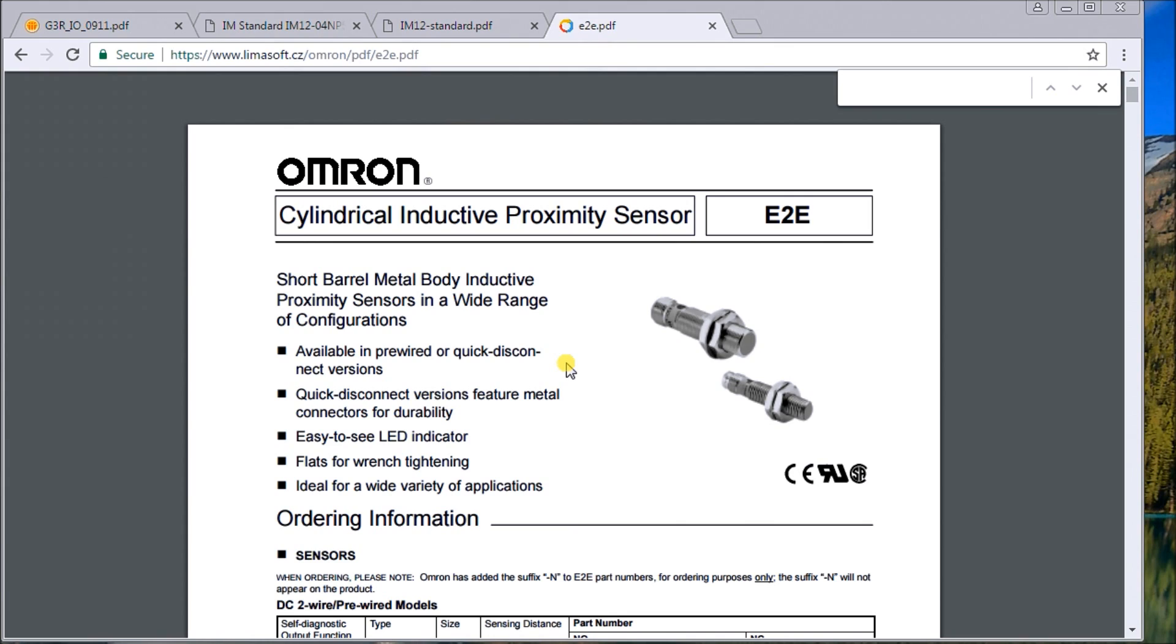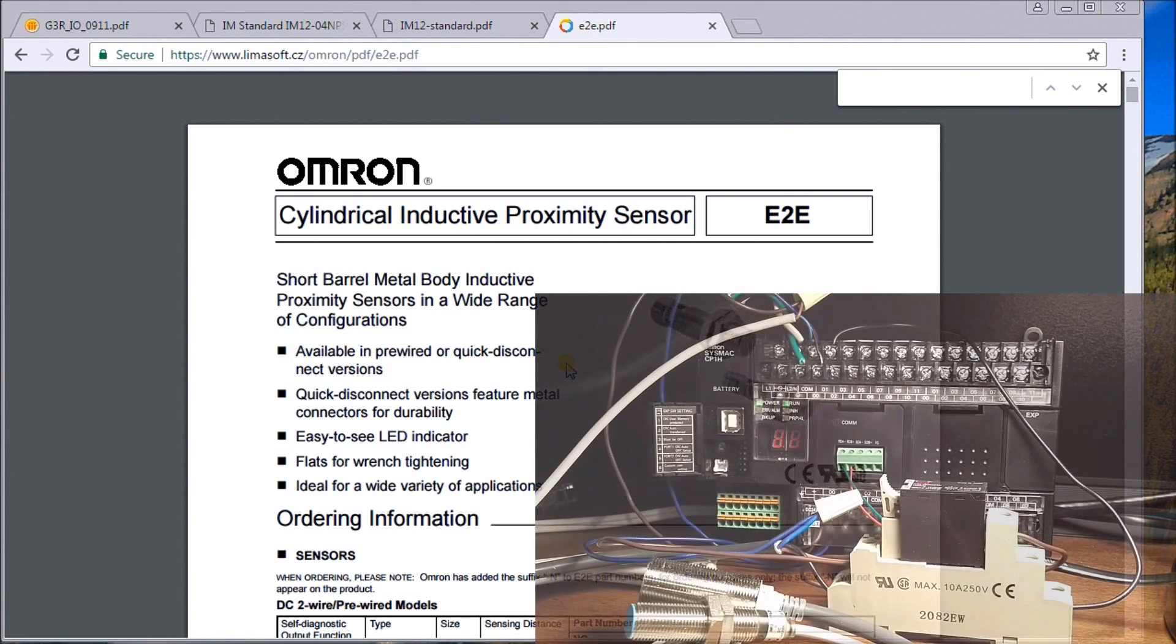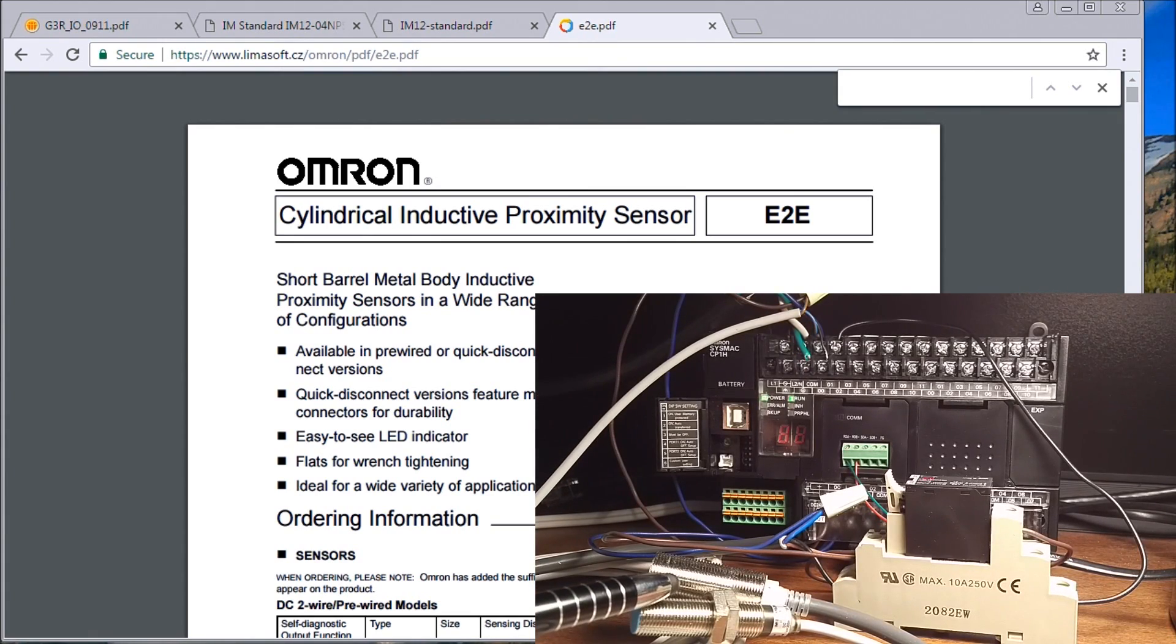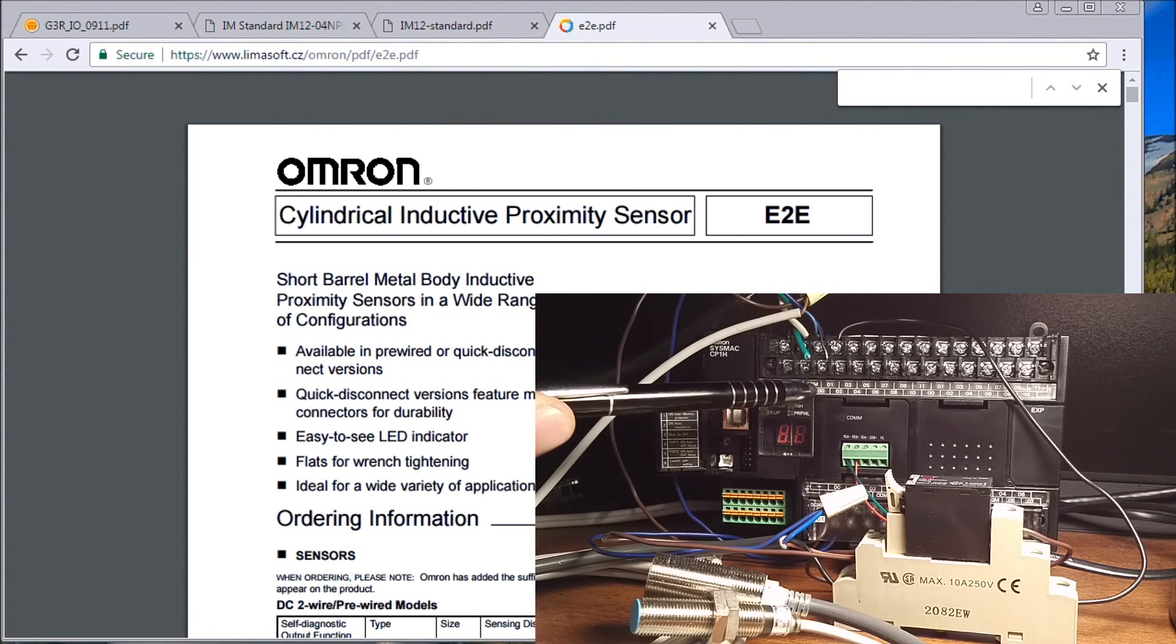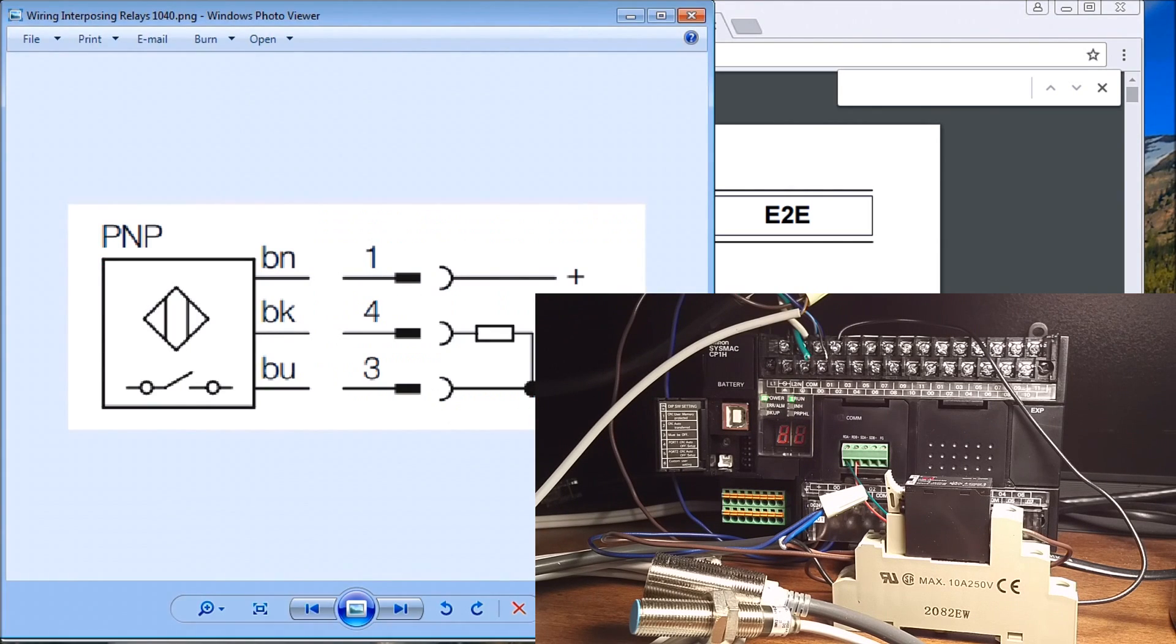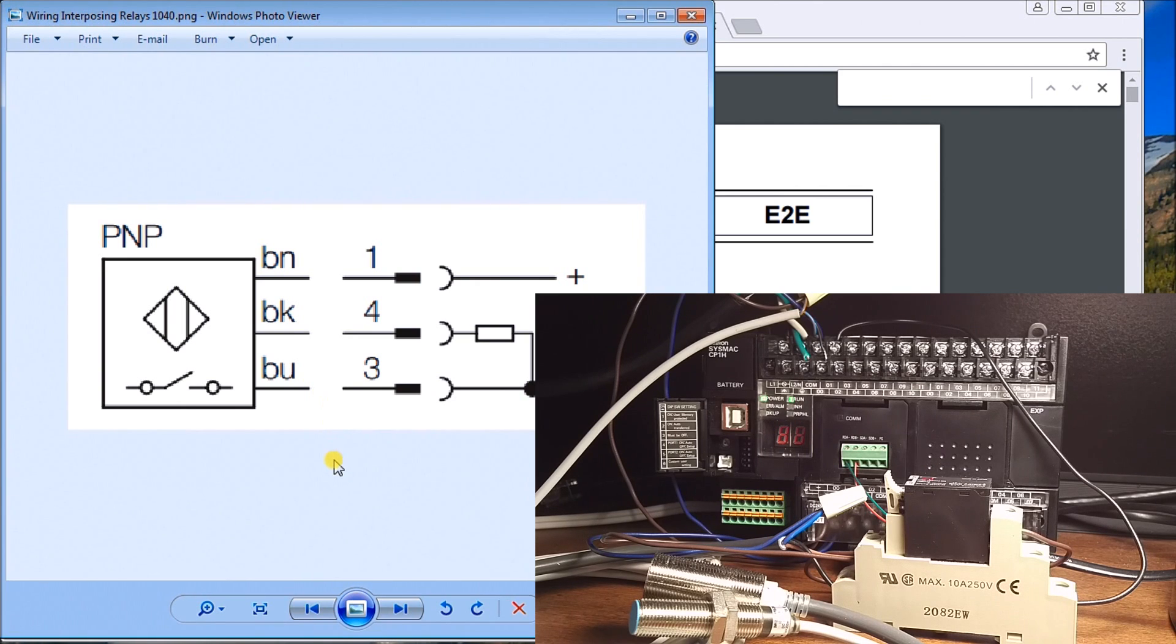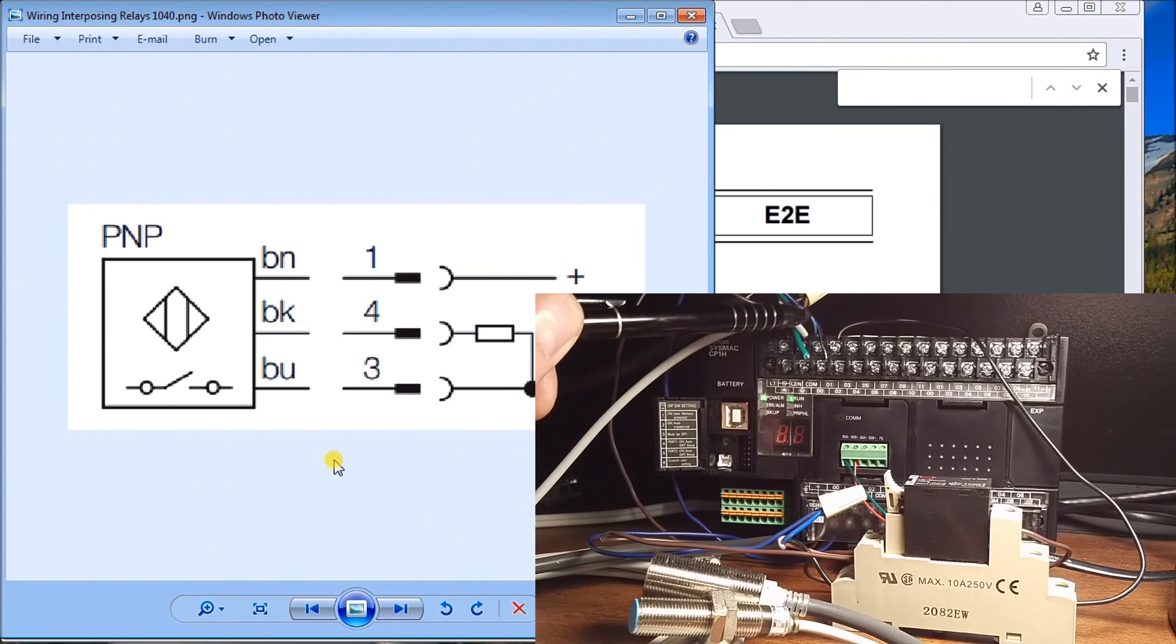Here's my SICK sensor wired into my first input zero. If we look at the wiring diagram, my load is between my black and my blue wire. My blue wire, which is my zero volts, is connected to my common, and my switching is my black wire which goes into zero.